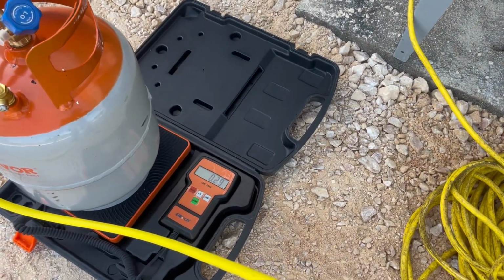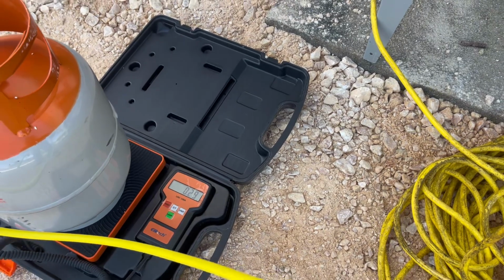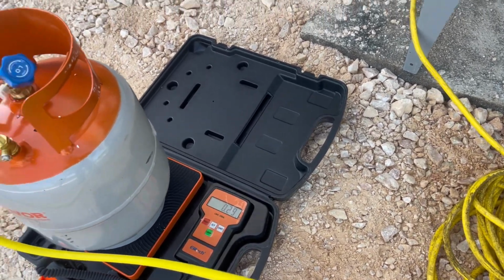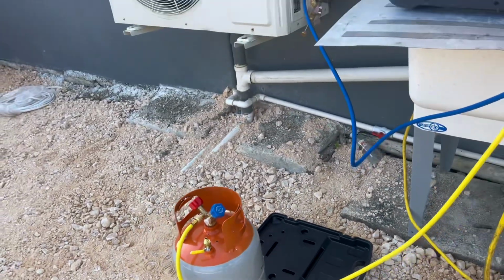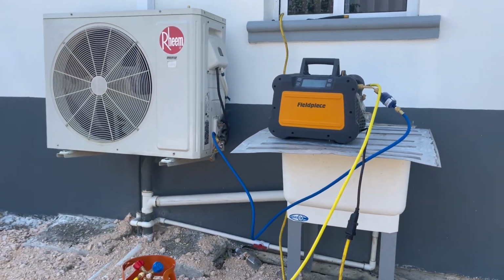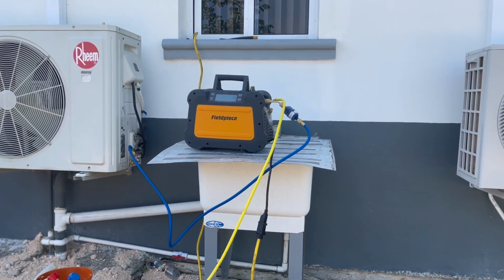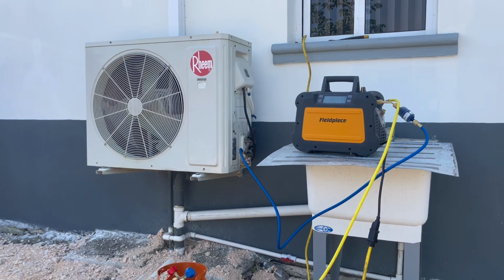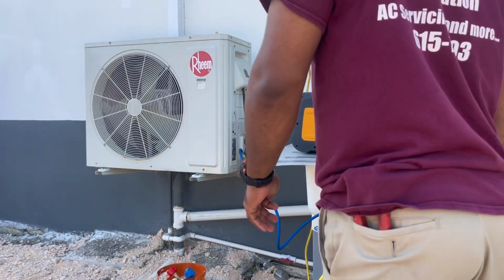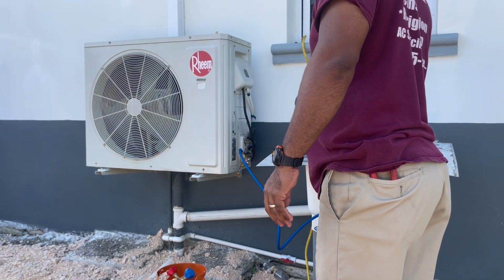We have to use a recovery machine to recover the freon out of the system because, like I said, the board was burned, so we cannot pump down the freon into the unit itself. So I have my Fieldpiece recovery machine, and this is how I set it up.